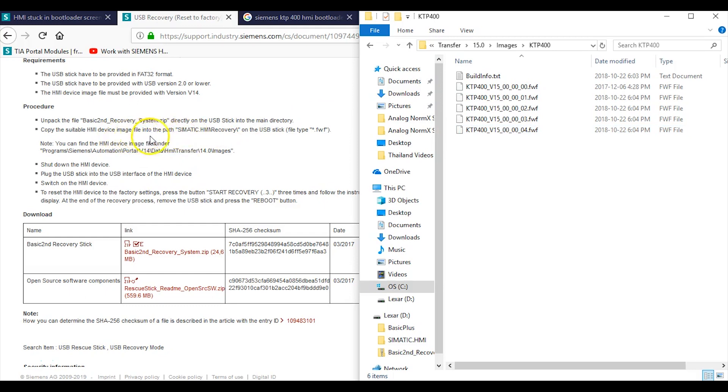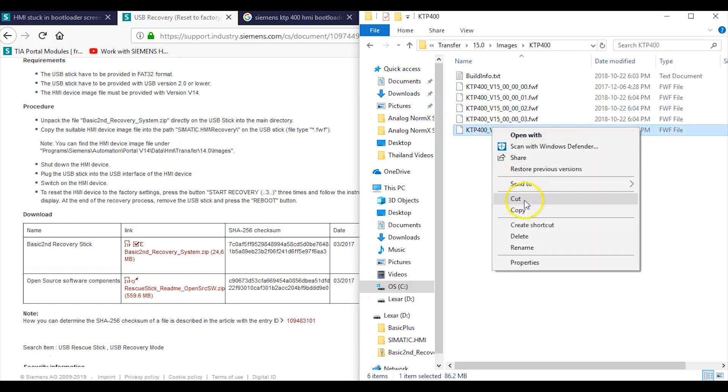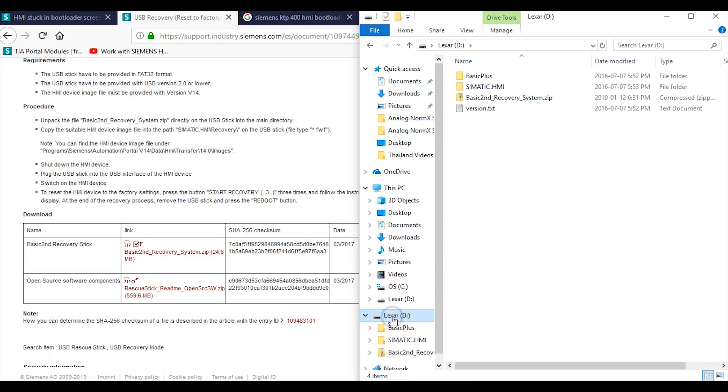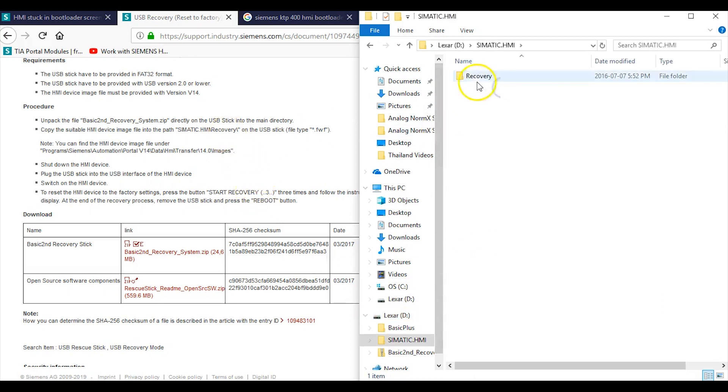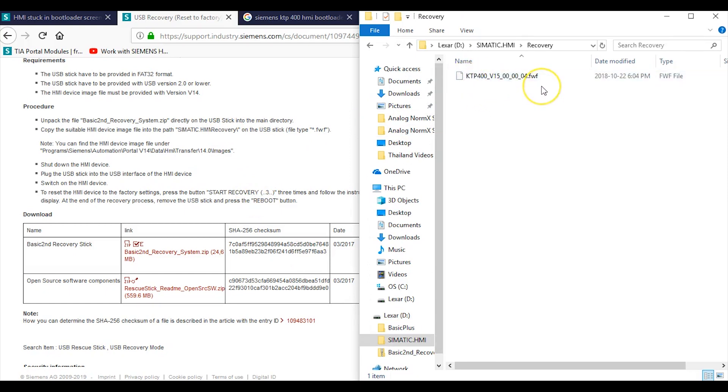There it is right there. I went with the newest version that I had from the last time that I updated Siemens TIA Portal. You're going to copy this file, and it says to put it where? Copy the image file into Simatic HMI Recovery. So again, you go here, you copy, then you go to your USB stick, you're going to Simatic HMI Recovery, and then you paste that bad boy right onto your stick. That's the image that you're going to download to your HMI.